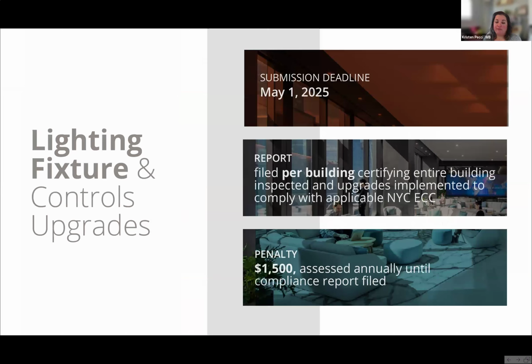So when talking about the lighting fixture and controls upgrade side of Local Law 88, the reporting side of this, the submission deadline, like we said before, is May 1st of 2025. Reports are going to be required to be filed per building, certifying that the entire building has been inspected and upgrades have been implemented to comply with the applicable New York City Energy Conservation Code. This report itself must come from either a professional engineer, a licensed electrician, or a licensed special electrician. So it has to be from one of those three types of professionals. It can't just be certified by a building owner or a building manager.